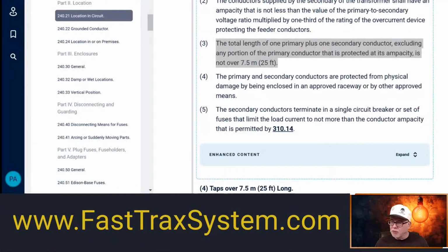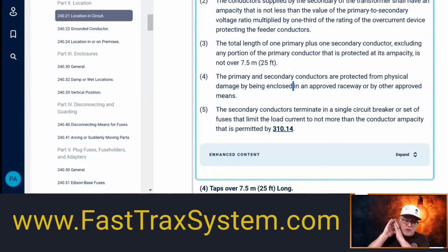Or not usually, in this case, it has to be if you want to use this rule, if you want to tap a feeder for your transformers. If not, just take your own separate line to your transformer, and you don't have to worry about this. But this is if you're tapping a conductor, tapping a feeder.